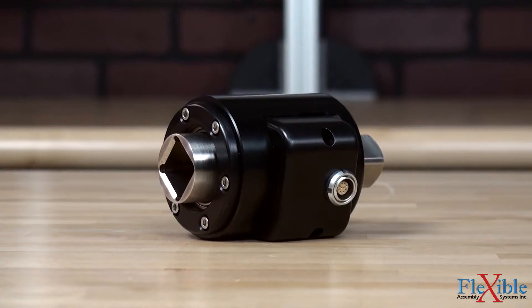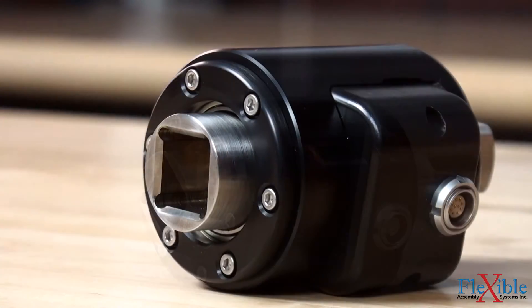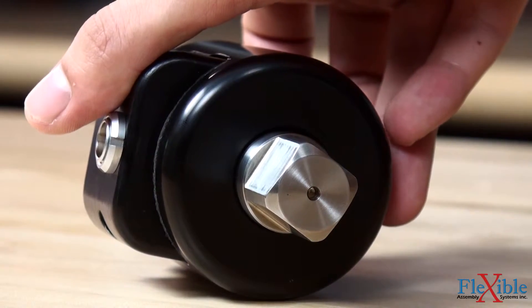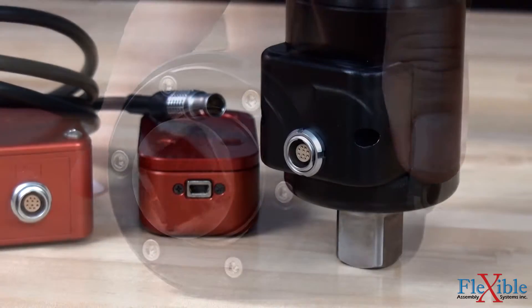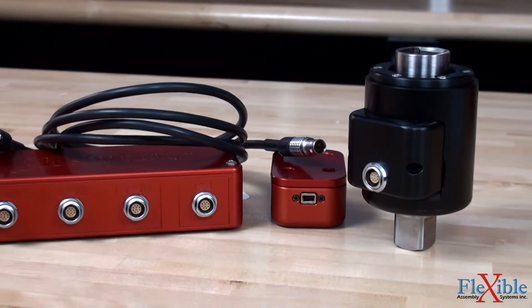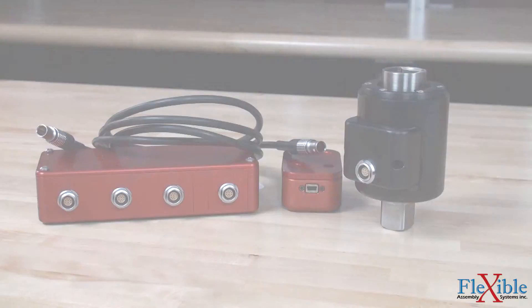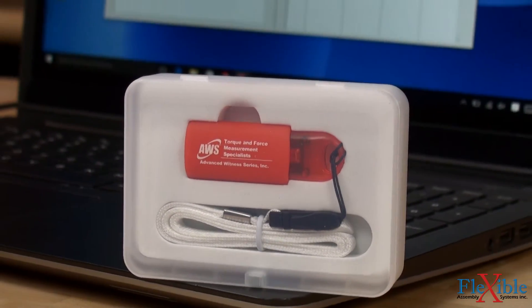AWS also offers a range of IRT impulse rotary transducers for bi-directional dynamic torque measurement. These strain gauge transducers are great for use with high RPM torque controlled nut runners without being adversely affected by frequency oscillations or joint rate conditions. IRT transducers are available in torque ranges from 100 pound-inch to 1000 pound-feet, with an accuracy of plus or minus 1% of the indicated reading from 20 to 100% of the transducer's range.